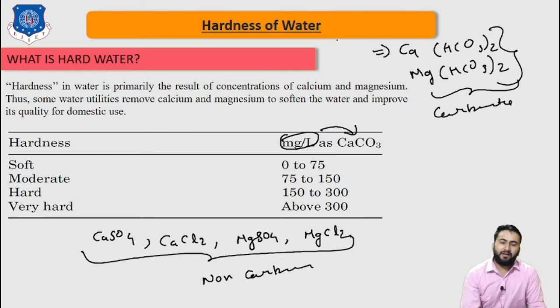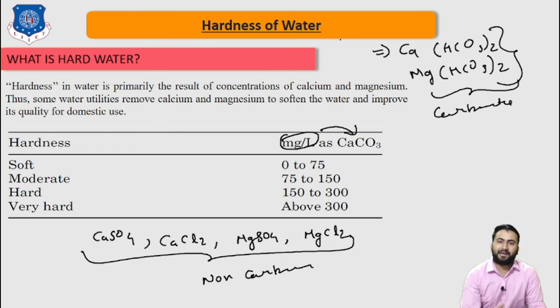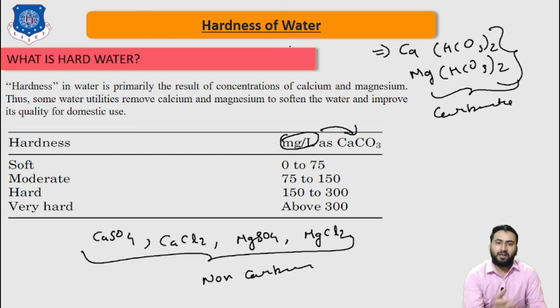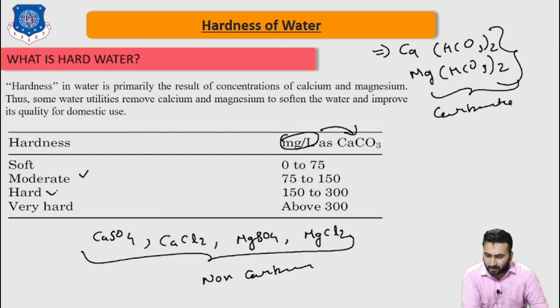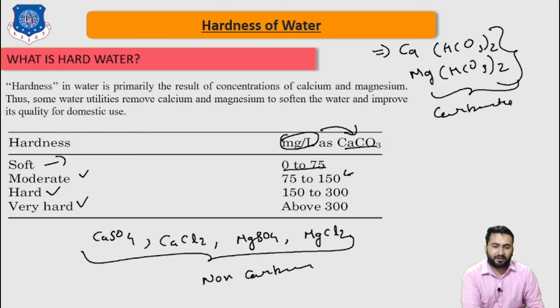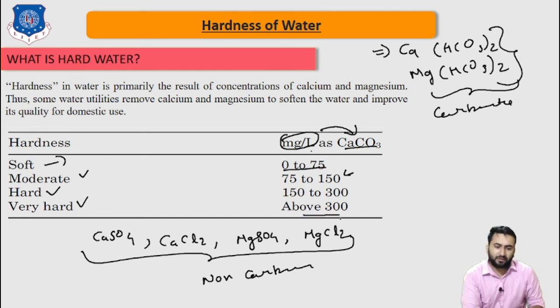For most applications, total hardness of 120 mg per litre or less and magnesium hardness of 40 mg per litre or less are acceptable design criteria for softening facilities. In general, the degree of hardness is classified as: soft (0–75 mg/L CaCO₃), moderate (75–150 mg/L), hard (150–300 mg/L), and very hard (above 300 mg/L). This is all about the hardness of water.